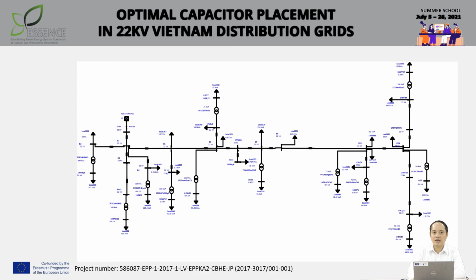Let's see. This is the medium voltage structure grid in Vietnam with a nominal voltage of 22 kilovolt. The request and objective is to determine the location to place the capacitor for reducing power losses in the medium voltage grid and to improve the voltage at the very end user of the line.